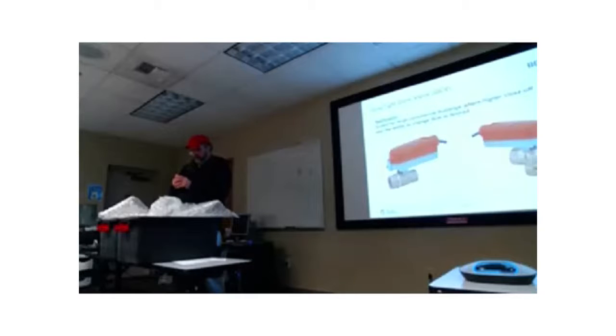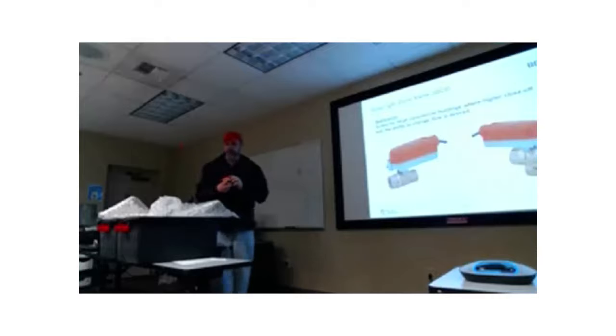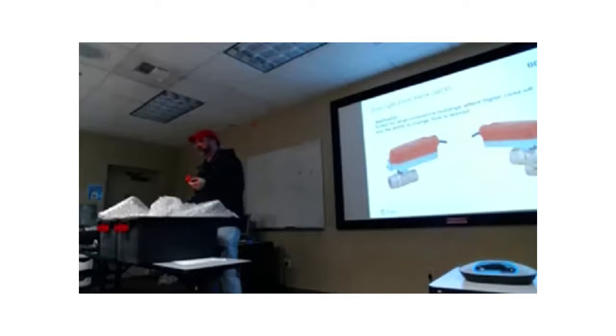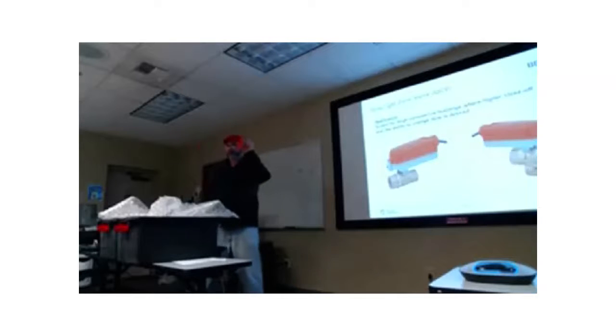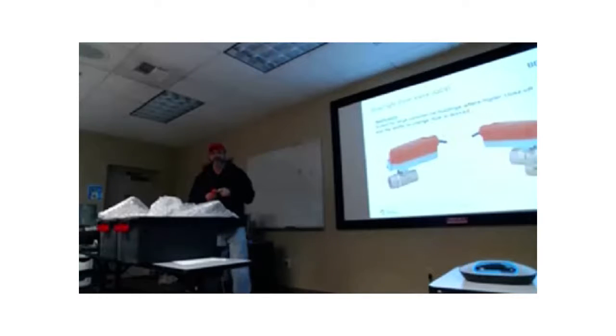The other thing about this, from an electrical point of view, because we have electrical installers here, is that this is a 2-position non-spring return valve. Just guess, what do you think the VA would be on this? I'm talking about the actual load, like your transformer load. 5 VA? Lower. Like 0.2? Higher. 0.5? A little higher. 0.6 VA, which is like nothing. So you've got an 80 VA transformer, you can put a lot of these on there. So that's one of the reasons we developed it.